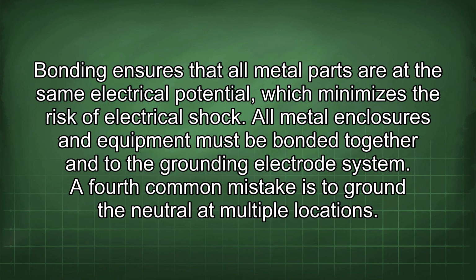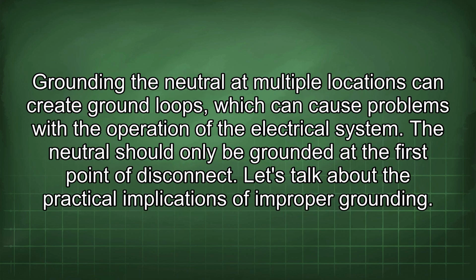A fourth common mistake is to ground the neutral at multiple locations. Grounding the neutral at multiple locations can create ground loops, which can cause problems with the operation of the electrical system. The neutral should only be grounded at the first point of disconnect.